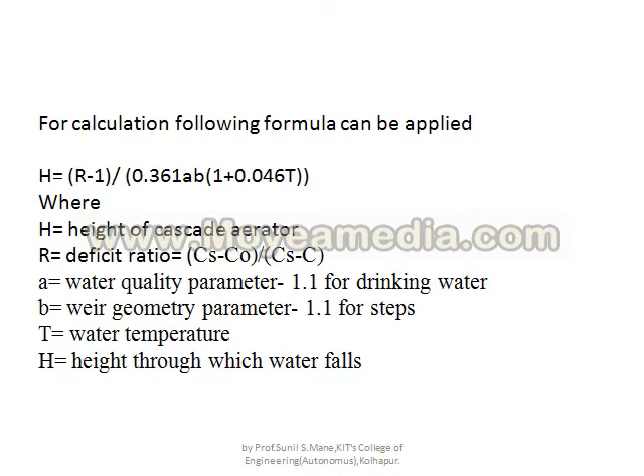The design calculation formula is: H = (R − 1) / (0.361 × A × B × (1 + 0.046T)). This formula may not be found in standard textbooks but is used for the best design of this type. H is the height of the cascade aerator, in meters.